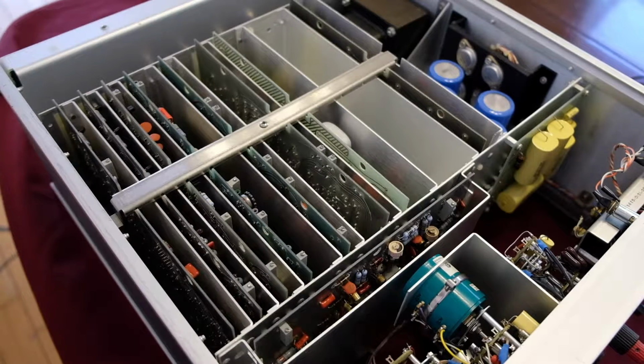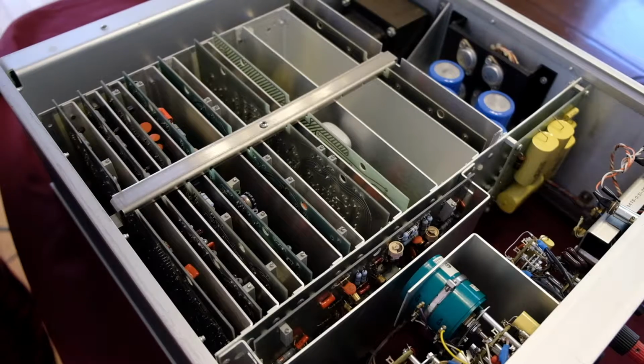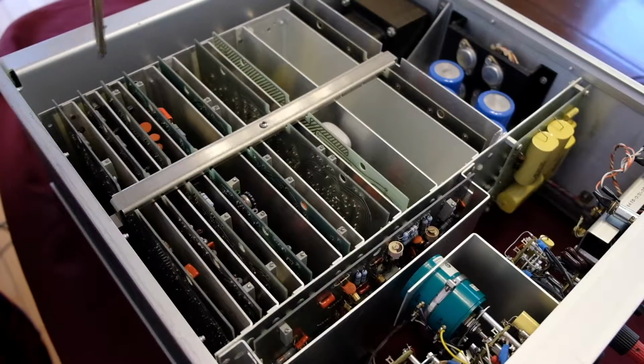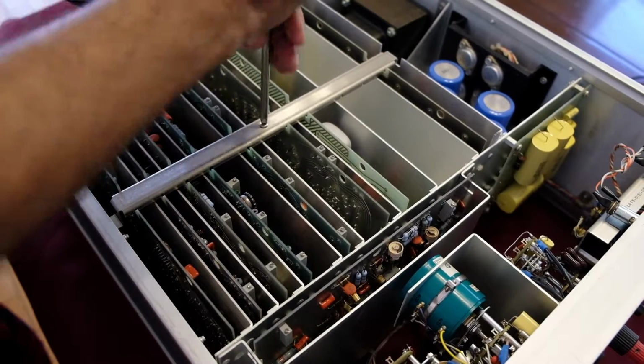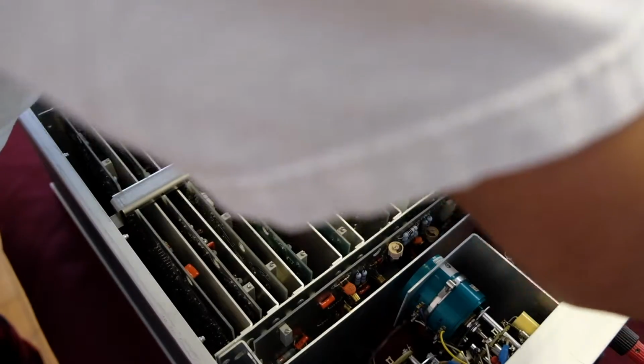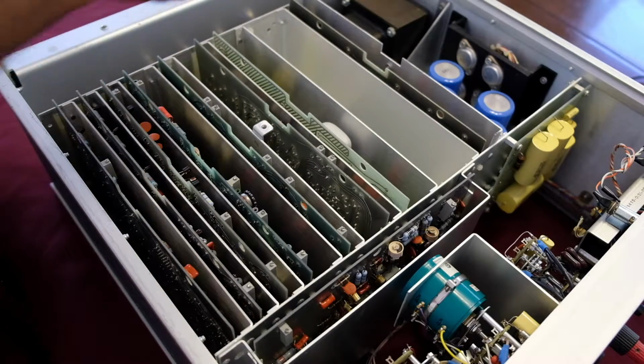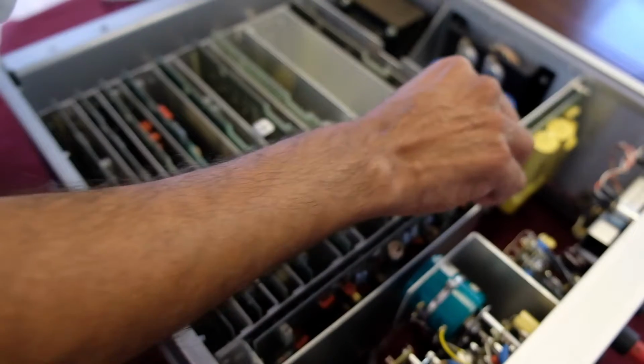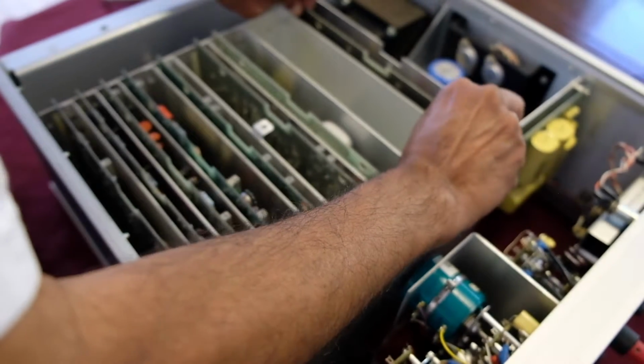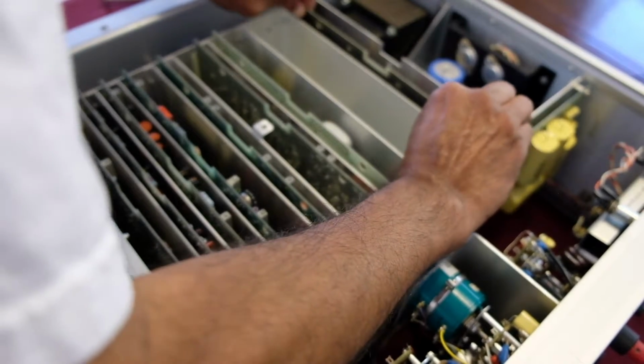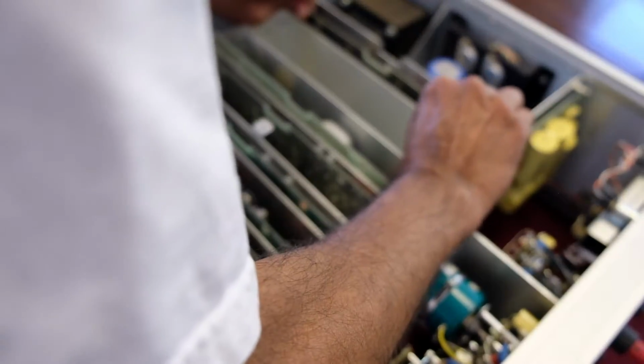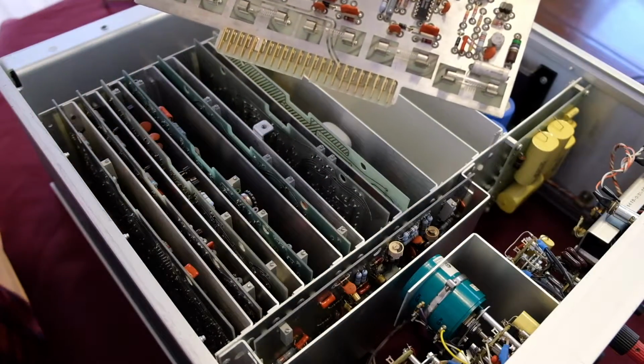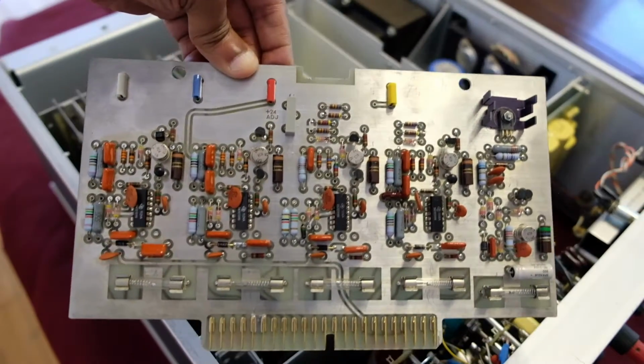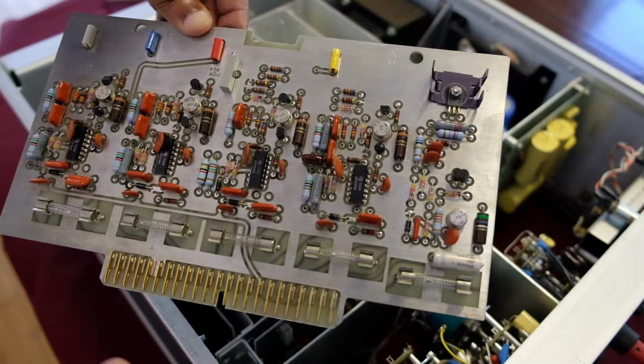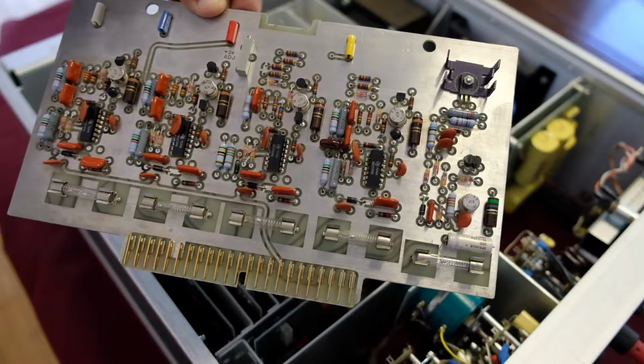Now back on the top side, I'm going to remove these cards and take a look at them. So the first thing is to remove this plate over here. Remove the power supply cord. So that comes off nicely. So the first card on the far side is this one, probably, not sure if I can. There it is. Looks like a power supply card. As you can see, there's a plus 24 volt adjustment, and since everything looks good, I'm not going to touch this card.